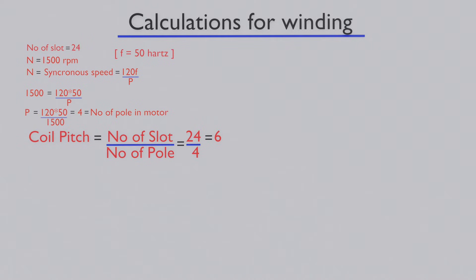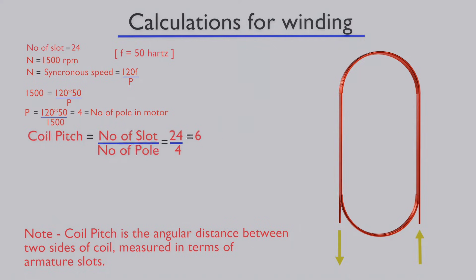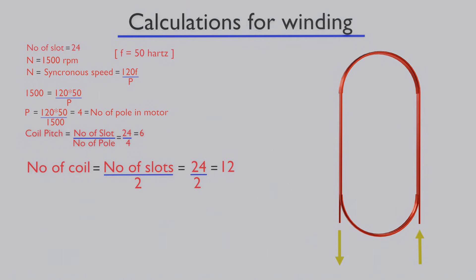Coil pitch is six for this winding. The coil pitch or coil span for winding is according to formula. It is the angular distance between two sides of a coil, measured in terms of armature slots. The number of slots is 24, so according to formula, we use 12 coils.